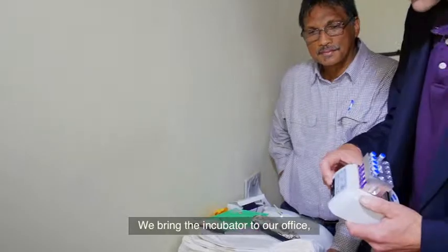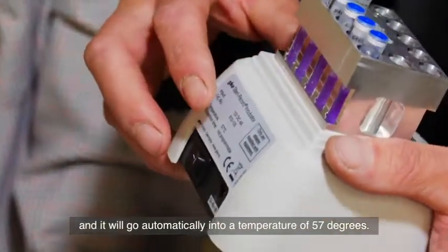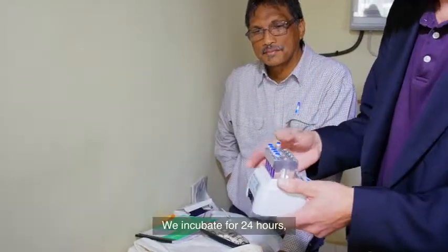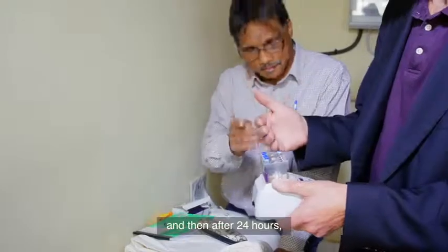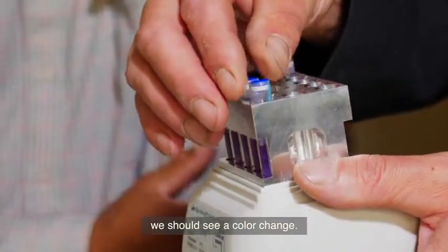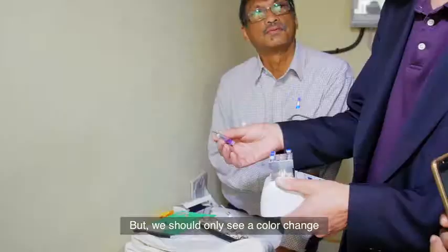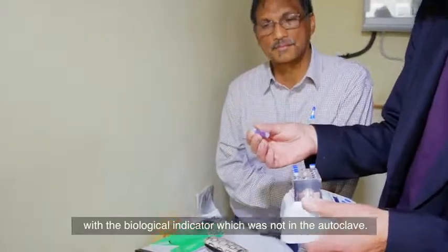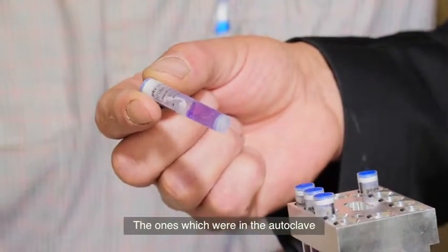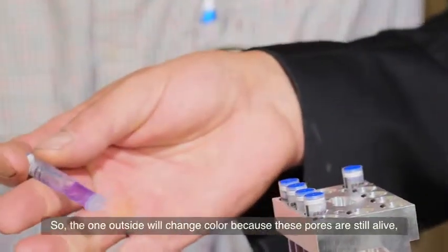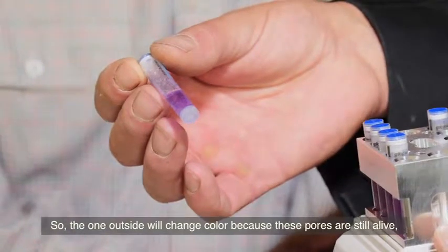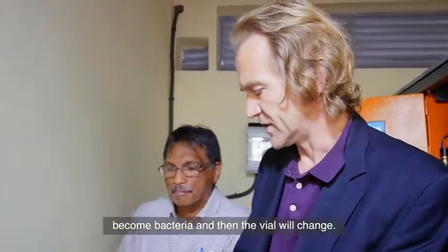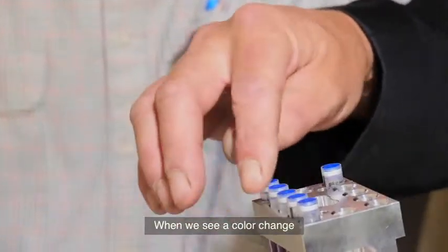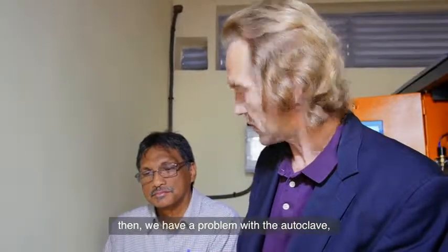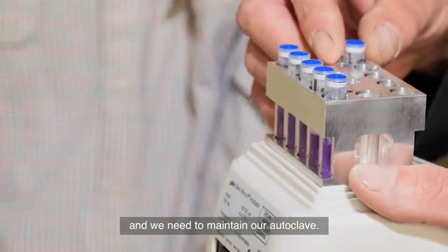We bring the incubator to our office, we switch it on, and it will automatically go to a temperature of 57 degrees. We incubate for 24 hours, and then after 24 hours, we should see a color change. But we should only see a color change with the biological indicator which was not in the autoclave. The ones which were in the autoclave will not change color because the spores are hopefully dead. The one outside will change color because the spores are still alive, become bacteria, and then the vial will change. When we see a color change of the ones which were in the autoclave, then we have a problem with the autoclave and we need to maintain our autoclave.